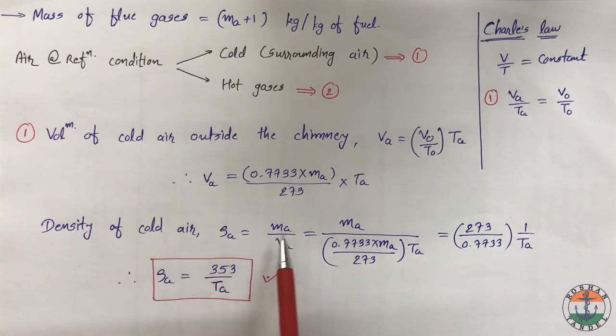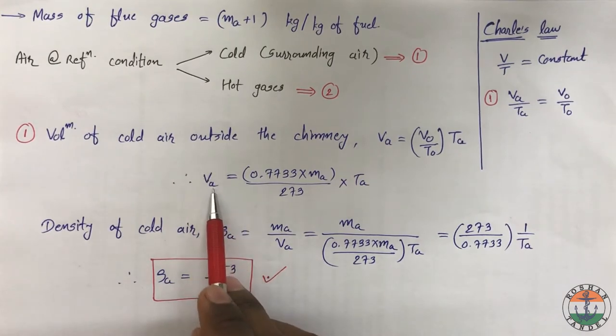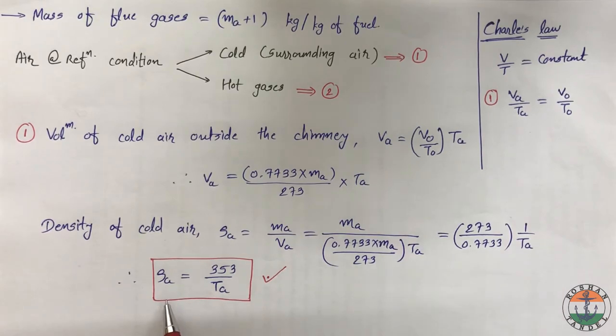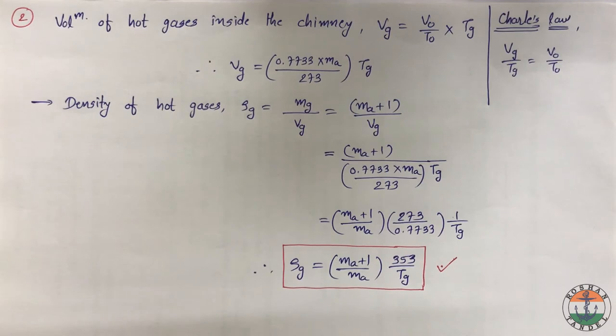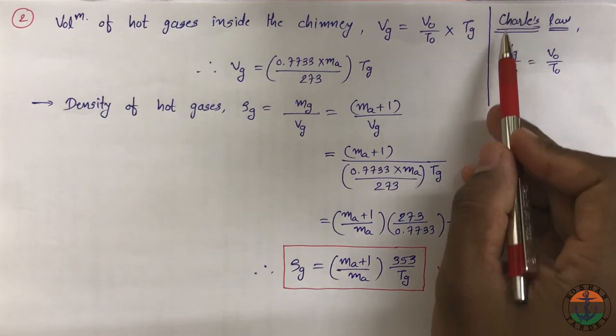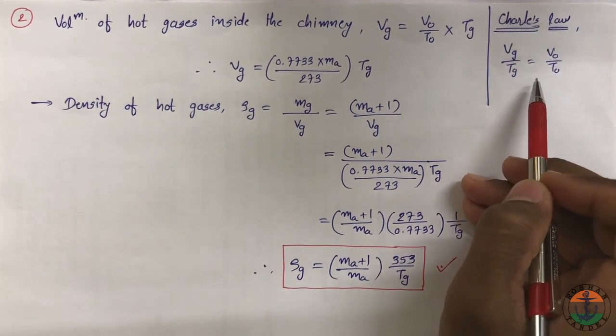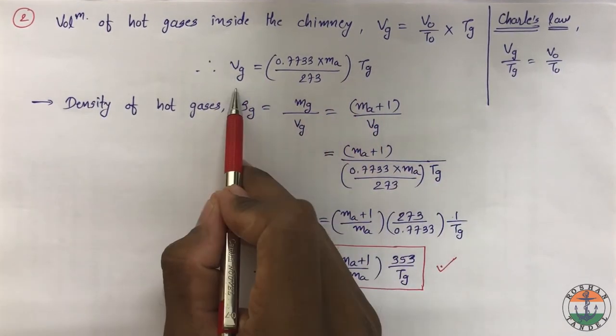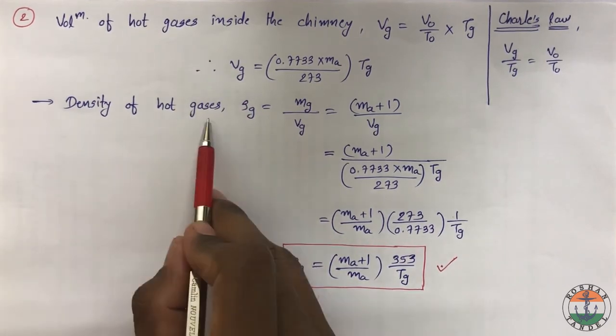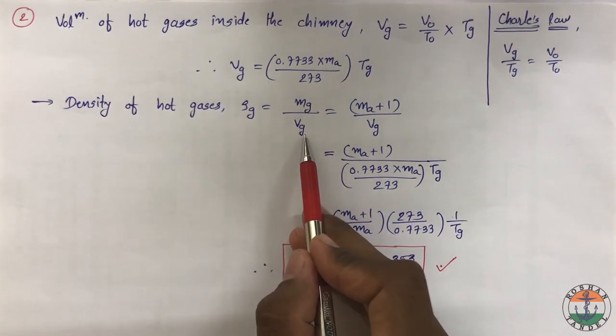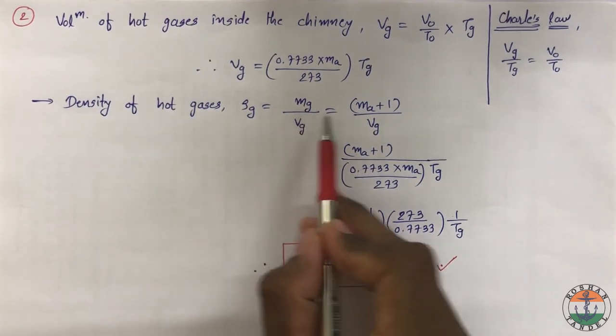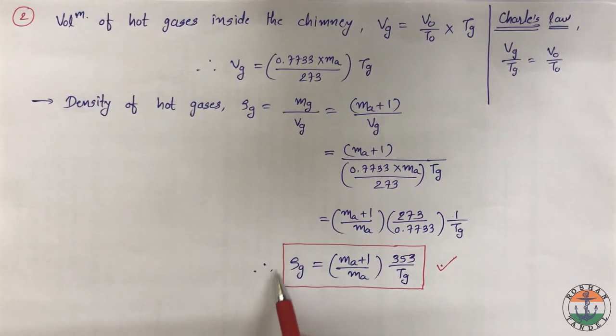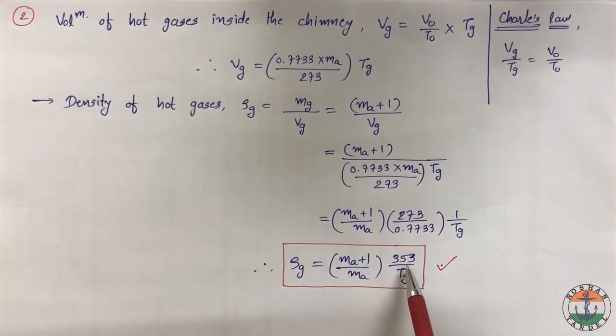Density of cold air rho_A equals Ma/VA. Substituting VA gives rho_A = 353/TA. For the second comparison, applying Charles' law to hot gases inside the chimney versus reference condition gives Vg = (V0/T0) × Tg. Density of hot gases rho_G equals Mg/Vg, where Mg equals Ma plus 1. The final value of rho_G becomes (Ma+1)/Ma × 353/Tg.